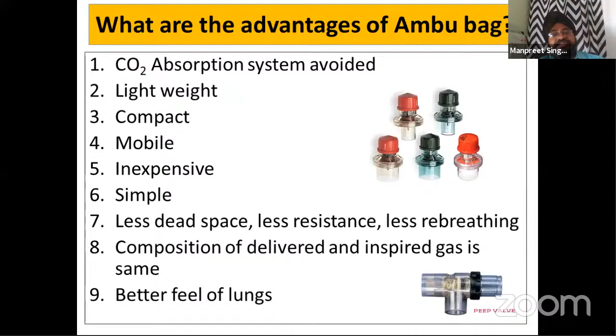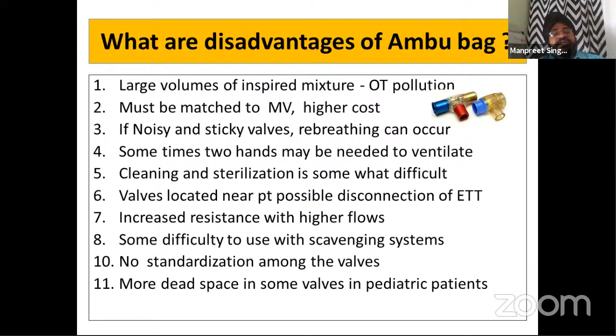What are the disadvantages? Disadvantages are large volumes of inspired mixture can be given, and it may cause OT pollution. Minute ventilation matching is very difficult to maintain. If noisy and sticky valves are there, then rebreathing can occur. Sometimes two hands may be required to ventilate. Cleaning and sterilization are a little cumbersome. You have to open the valves and then you have to clean those valves. Otherwise, there can be stickiness of these valves. Increased resistance with higher flows and some difficulty to use with a scavenging system. There is no standardization among the valves.